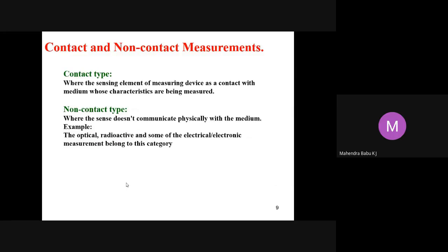We also have contact type and non-contact type of measurement. In the contact type, the sensing element of a measuring device has contact with the medium whose characteristics are being measured, whereas in the non-contact type, the sensor does not have any physical contact with the medium. For example, optical, radioactive, and some of the electrical or electronic measurements belong to this category.